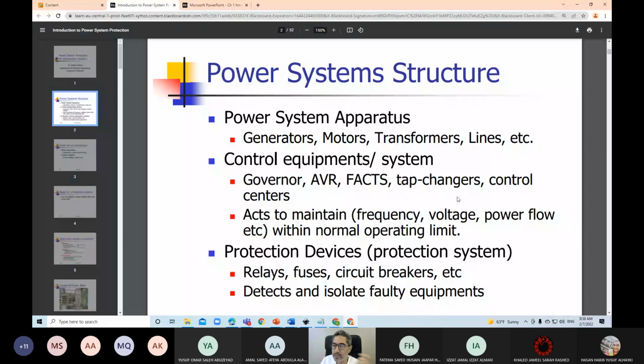We have control systems that maybe control the power flow in the system, or they control at what situation you should switch on a new generator, at what situation you should switch off a generator from the system, so that the system becomes reliable, okay, and secured. But the main purpose of the control system is to maintain the frequency, the voltage, the power flow within the normal operating limits, within the safe limits, okay?